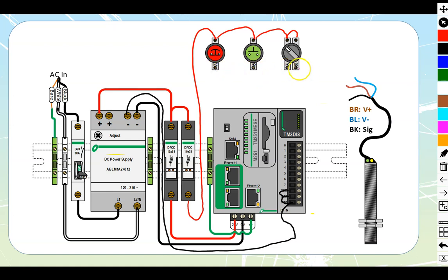Last thing that we would do is then we would just take an input from each of these. We've got a normally closed stop, normally open start. We've got selector switches over here. You would just run inputs from these down to your PLC, terminating them inside of each of these individual sections. So we'll run these out. So at this point, we've got a bunch of discrete inputs. They're going to be on or off type of inputs that we would have using these ones over here. We see that we've got our negative carried all the way through. And if we follow through our path for power, you always need to be able to form a complete path for power. Positive going through, pick a field device to go through. We'll go through this normally closed. Hitting the input card, going through the card and coming back on the negative to your power supply over here. That reference that we have. It's important that you have that complete path all the way through.